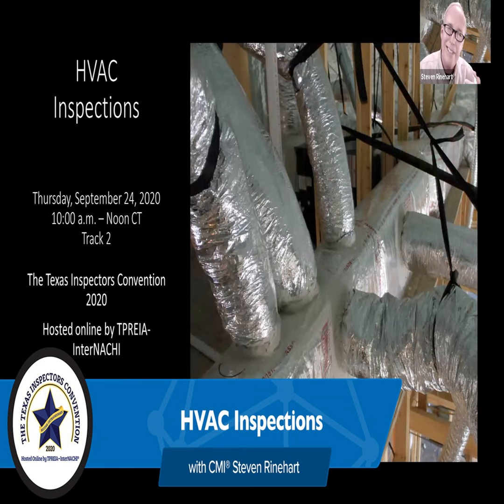The challenge is with newer houses, we are creating pressure imbalances with kitchen exhaust fans that go outside, bathroom exhaust fans. The ductwork itself changes the pressure in the house. That unit may shoot 2,000 CFM into the attic to send to all the rooms, but it leaks like a wicker basket, and you only get back 1,500 CFM because you leak 500 CFM in the attic.